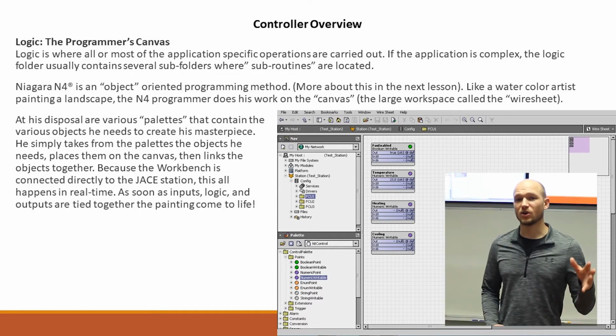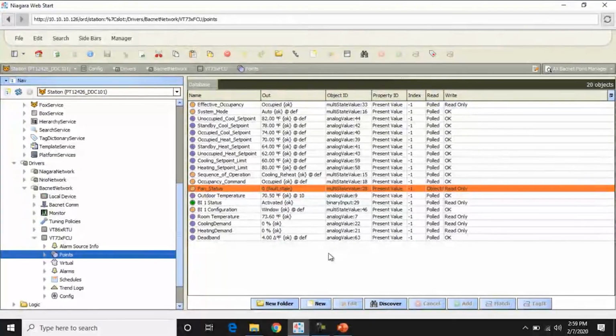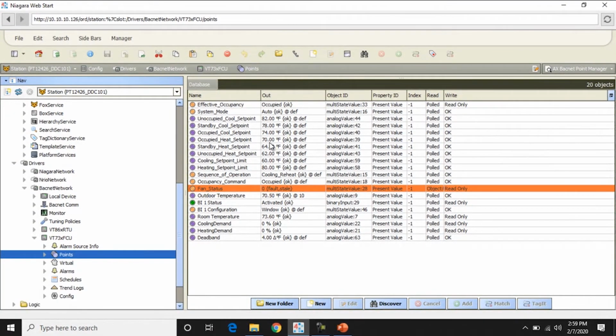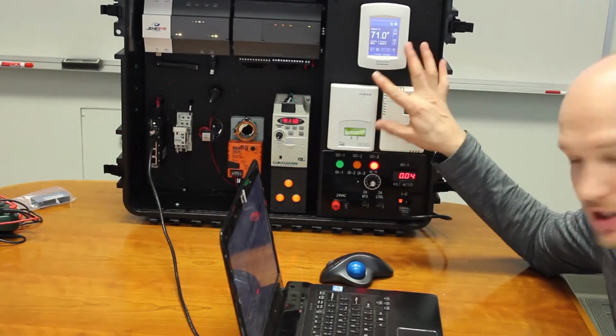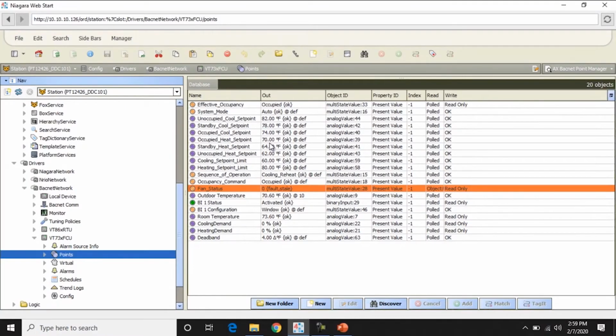So Niagara N4 is an object-oriented programming method. The occupied heat set point, right? At 70 degrees. This is a physical and virtual point that can be adjusted locally at the device, right? We can adjust it here, or we can adjust it or command it written by the JACE, allowing the set point to be adjusted remotely.